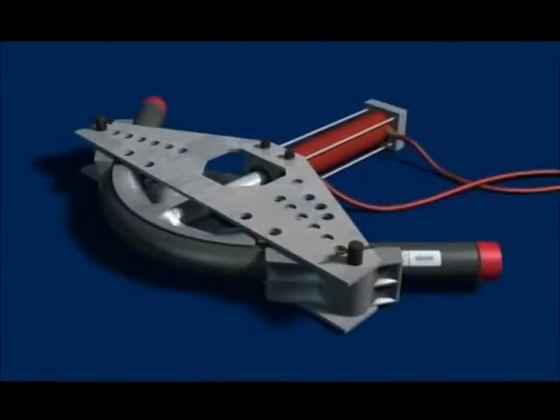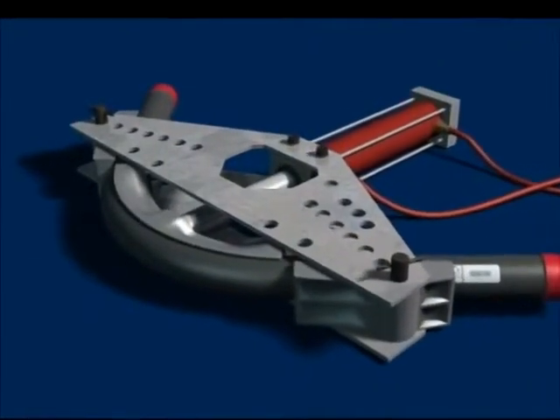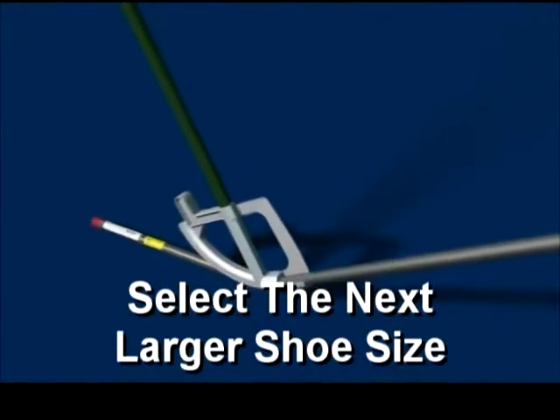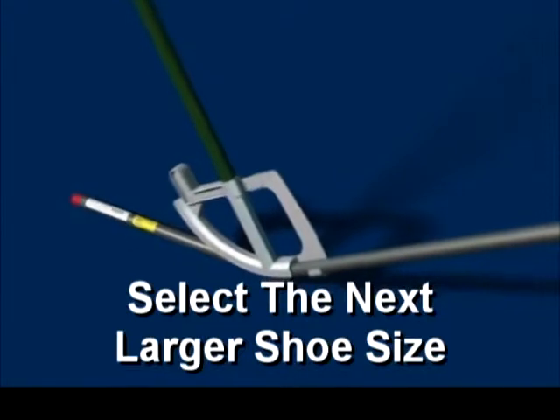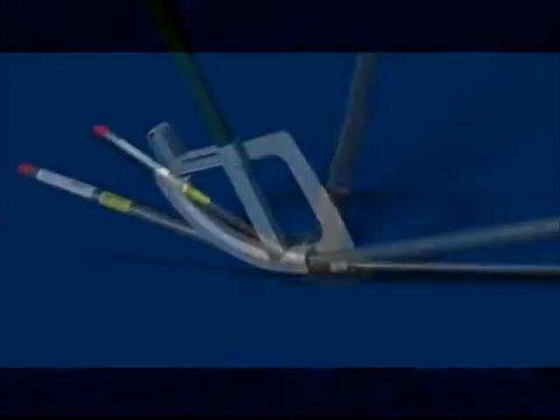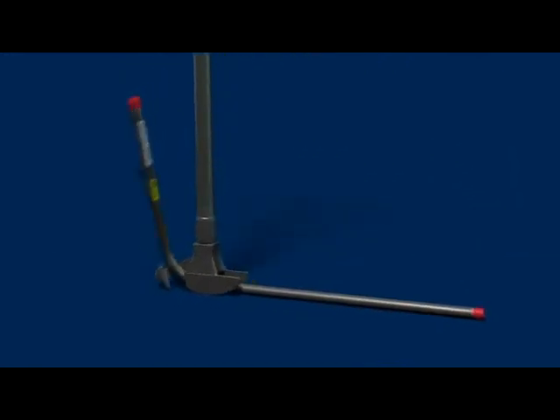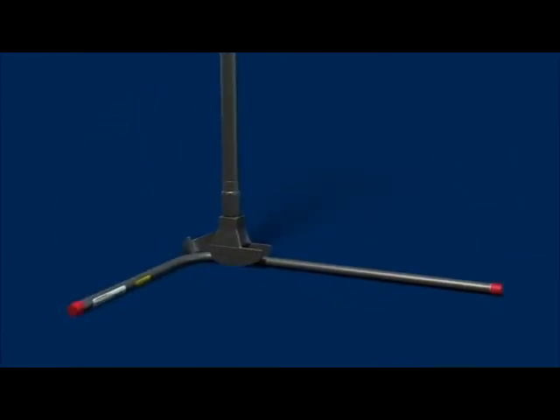PlastiBond coated conduit can be bent with conventional bending equipment. To accommodate the PVC coating when using a hand bender, always select the next larger size shoe. Use a PlastiBond hickey to reduce the possibility of damage to the conduit coating when making sharp bends, saddles or offsets.